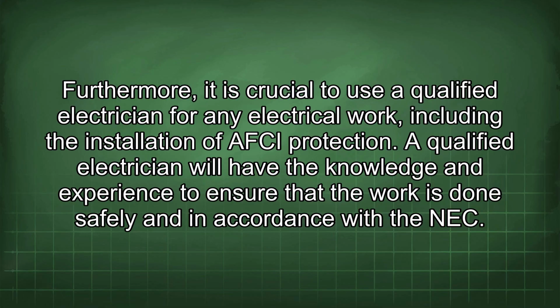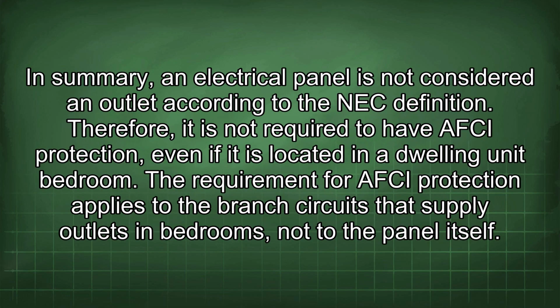In summary, an electrical panel is not considered an outlet according to the NEC definition. Therefore, it is not required to have AFCI protection even if it is located in a dwelling unit bedroom. The requirement for AFCI protection applies to the branch circuits that supply outlets in bedrooms, not to the panel itself.